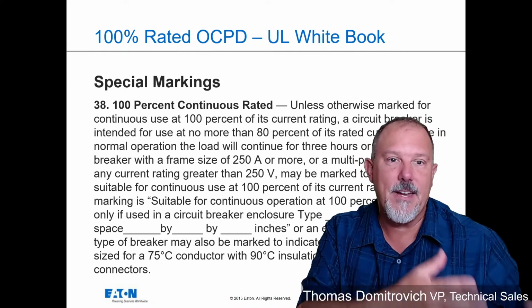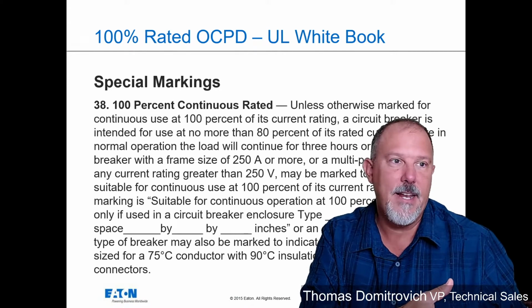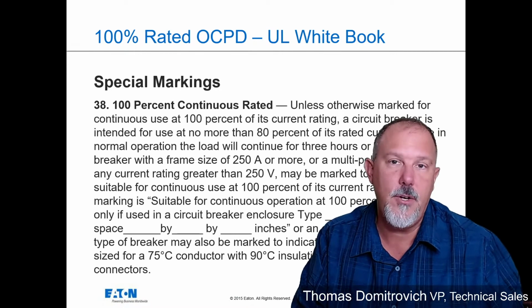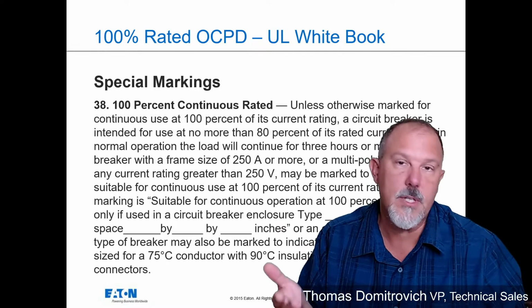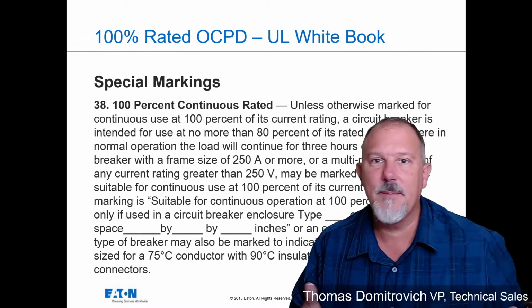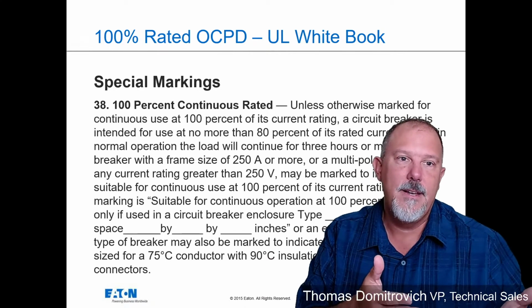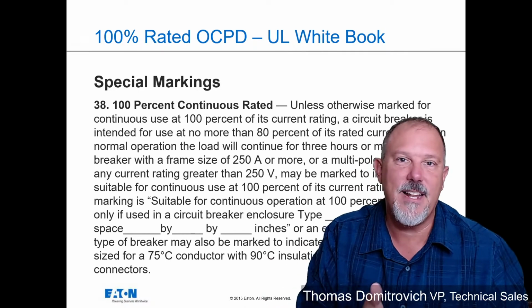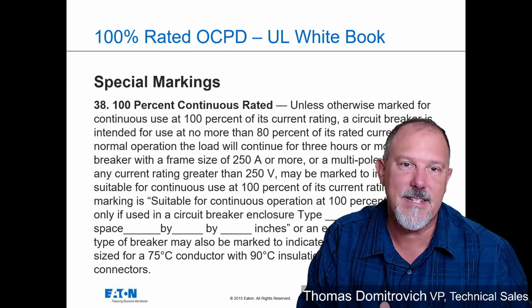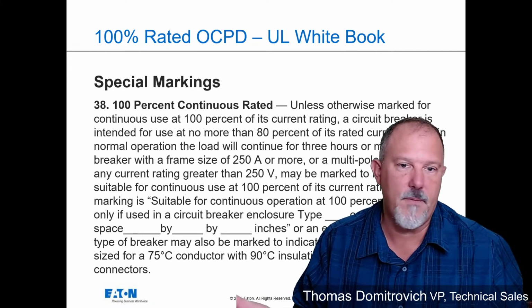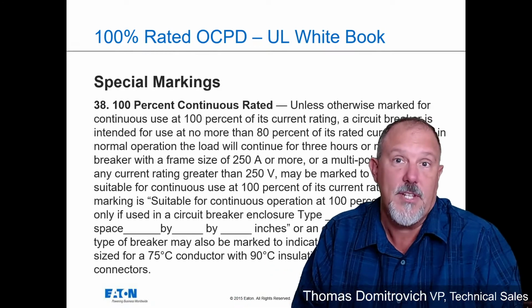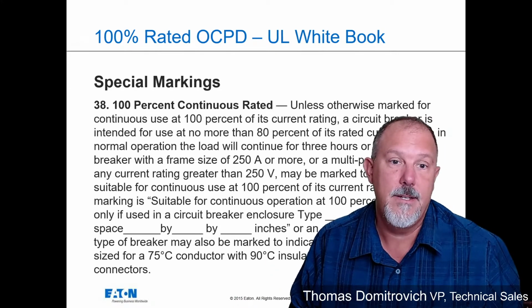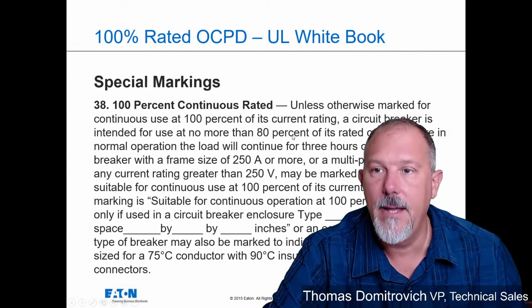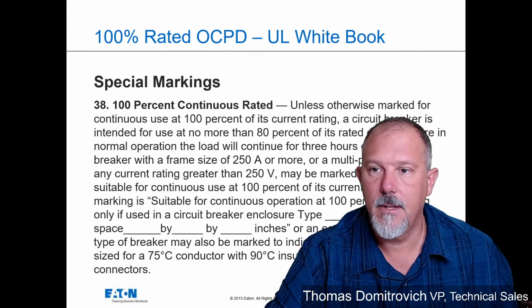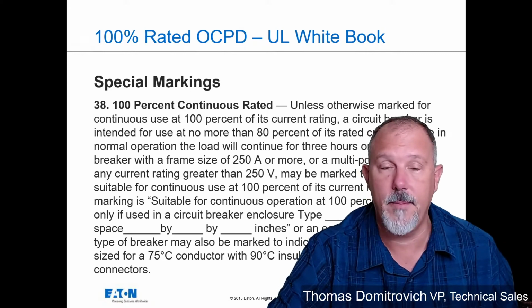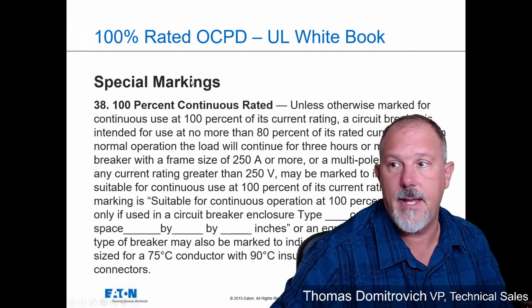So if I do my calculations and I have 1600 amps of continuous loads, then I put it on a 2000 amp breaker, put 1600 amps worth of conductor, and adjust it down to 1600 amps. I don't see what the issue is. I'm perfectly fine. It's an 80% rated breaker, and you're using it at 80% of its rating. That's where my head's at, and the more I think about it, that's where I'm at. I think you're perfectly fine in that application.